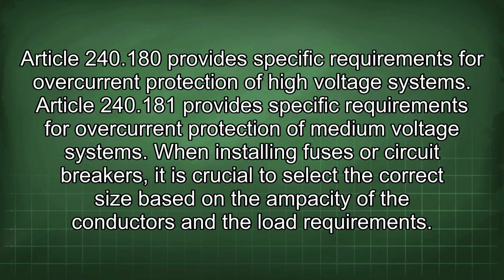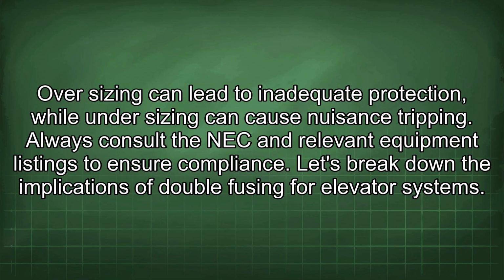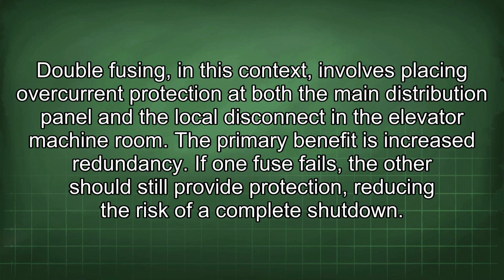When installing fuses or circuit breakers, it is crucial to select the correct size based on the ampacity of the conductors and the load requirements. Oversizing can lead to inadequate protection, while undersizing can cause nuisance tripping. Always consult the NEC and relevant equipment listings to ensure compliance. Let's break down the implications of double fusing for elevator systems. Double fusing, in this context, involves placing overcurrent protection at both the main distribution panel and the local disconnect in the elevator machine room. The primary benefit is increased redundancy. If one fuse fails, the other should still provide protection, reducing the risk of a complete shutdown.